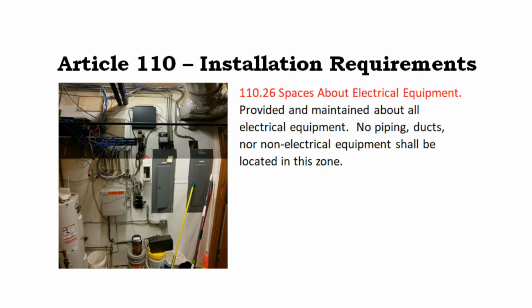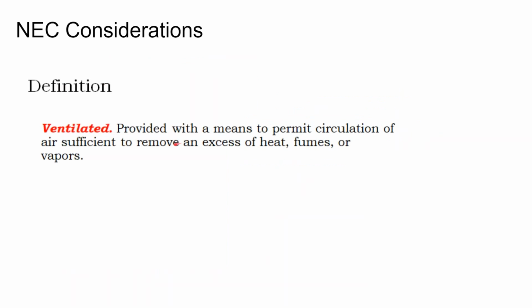That space can be right next to other utilities though. Generally speaking, from the floor up you need about 6 feet of room, and then you can have your air conditioning duct, or a gas line can be right at the side of your equipment. As long as you have enough clearance to work on that side, you can have your gas line on the other. But you can't have, say, a gas line running underneath where the service panel should be, because that would be a space violation. You really need dedicated working area around your electrical equipment.